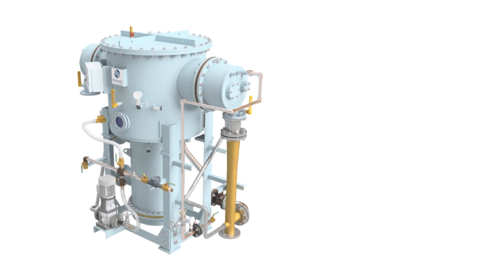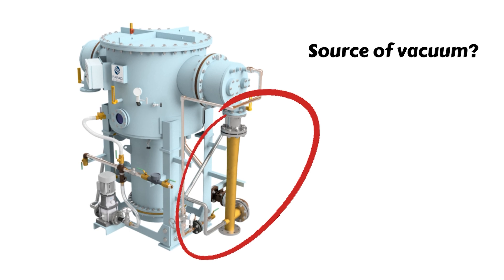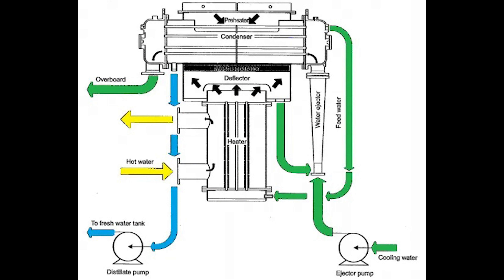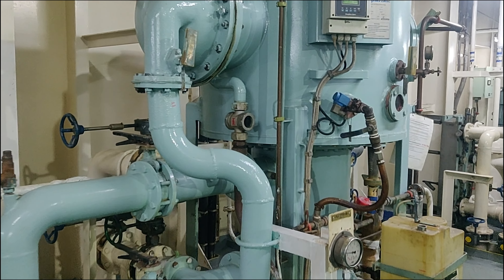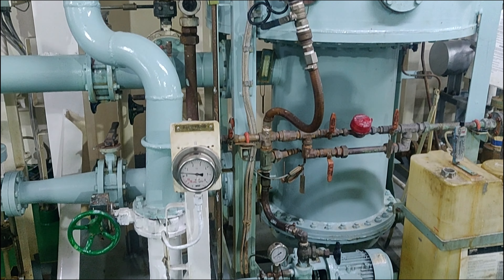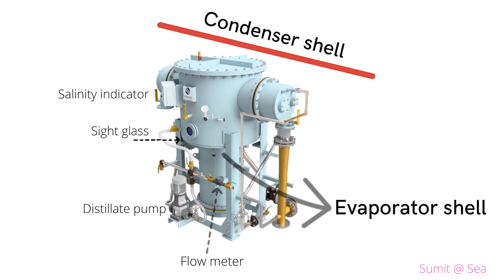For producing fresh water at sea, we need: number one, seawater; number two, a heat source; and number three, a source of vacuum. Seawater is easily available at sea. The heat source for the fresh water generator is the waste heat rejected by the main engine jacket cooling water. The combined air-brine ejector creates vacuum in the evaporator shell by continuously driving out air and brine. Using energy from the heating coil and by reducing pressure inside the evaporator shell, boiling can take place at around 40 to 60 degrees Celsius.